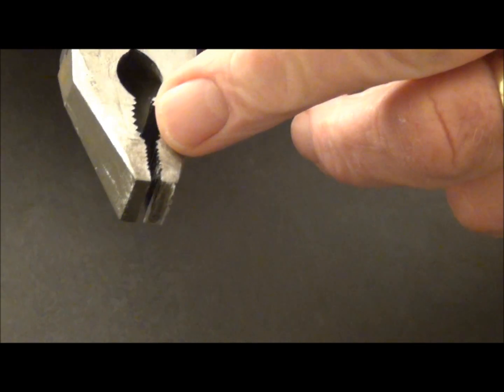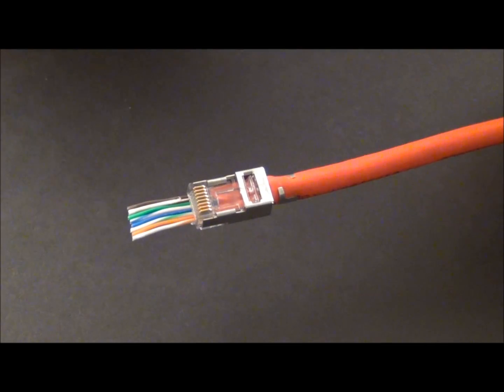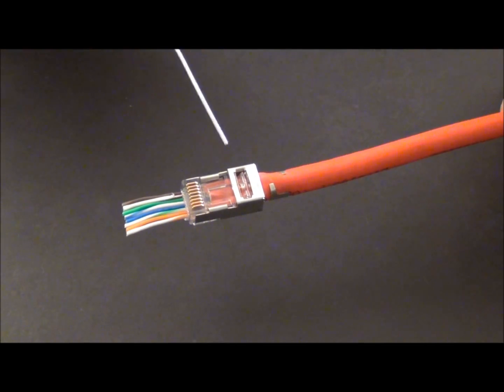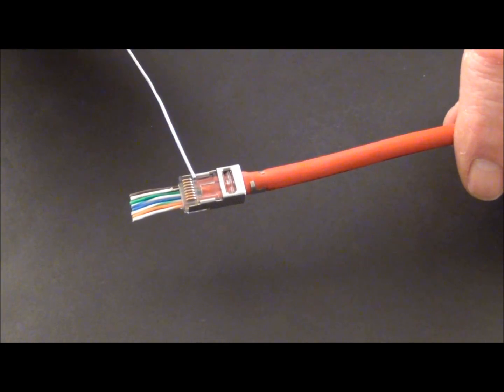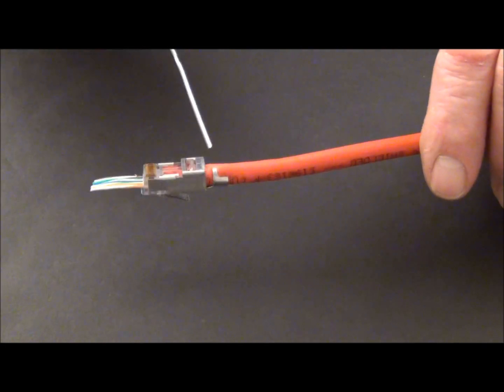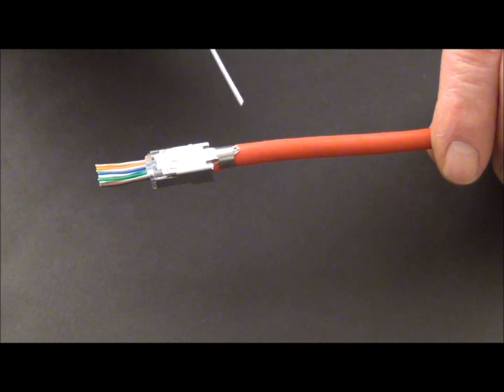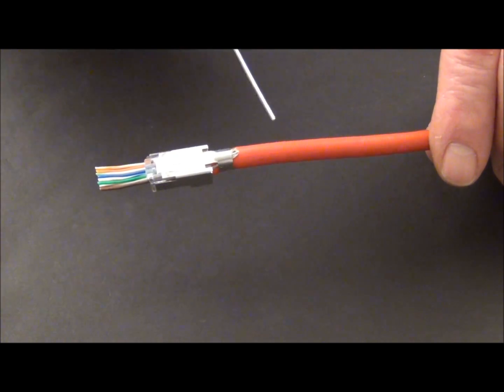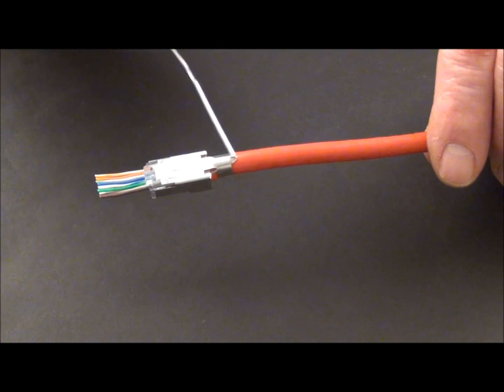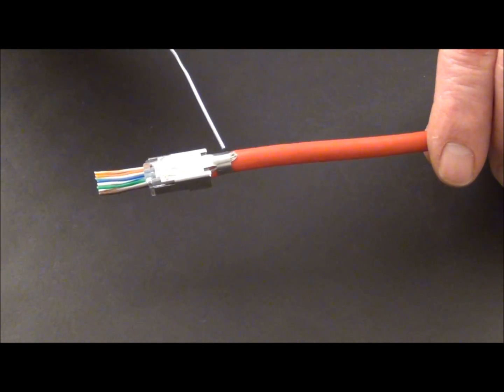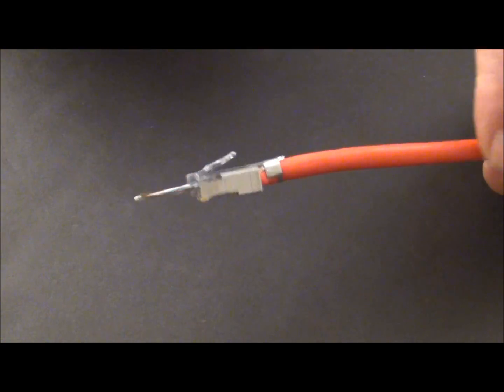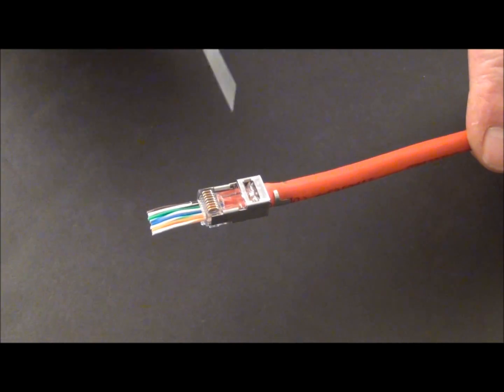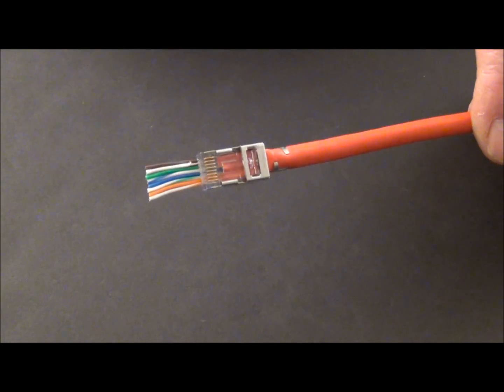Okay, so here we are ready to be terminated in the tool. I'm not going to terminate it, but here's the connector ready to go. Again, the twist up here to the back of the contacts. That's Cat 6. And here's your external ground. Notice I couldn't use the foil because the cable is at its max. Just no way would the foil and the cable fit. But I relied on the drain wire and I rolled it up into a little mass right here. It's rolled up three times and that's where the ground is taking place. So there's your finished crimp ready to be, I mean, RJ-45 shielded external ground Cat 6. Thanks.